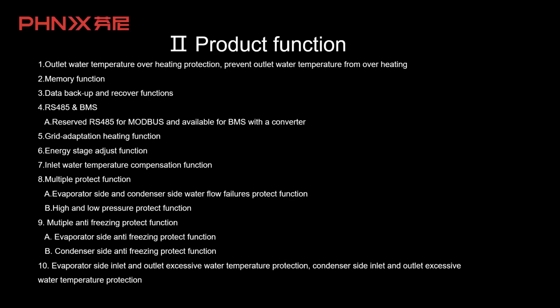Number 7, inlet water temperature compensation function. Number 8, multiple protect function: A, evaporator side and condenser side water flow failure protect function; B, high and low pressure protect function. Number 9, multiple anti-freezing protect function, both evaporator side and condenser side anti-freezing protect function. Number 10, evaporator side and condenser side inlet and outlet excessive water temperature protection.